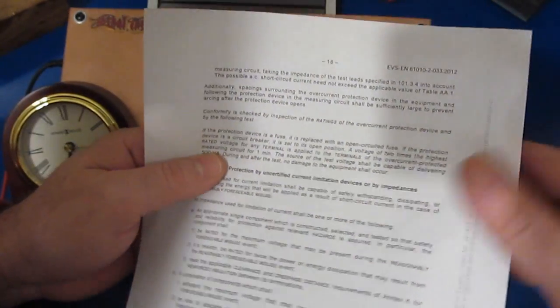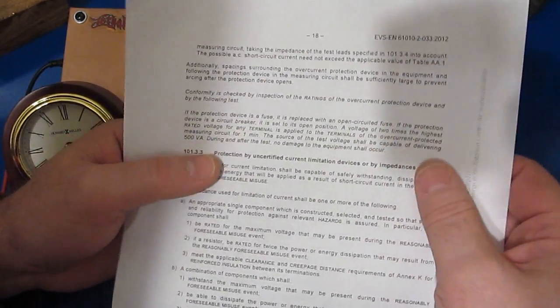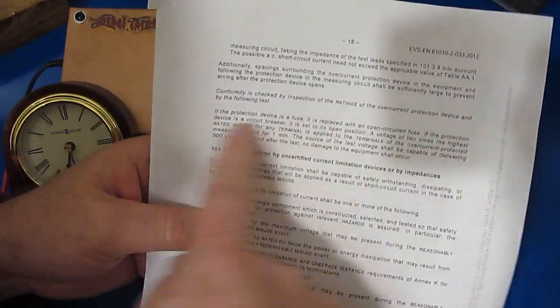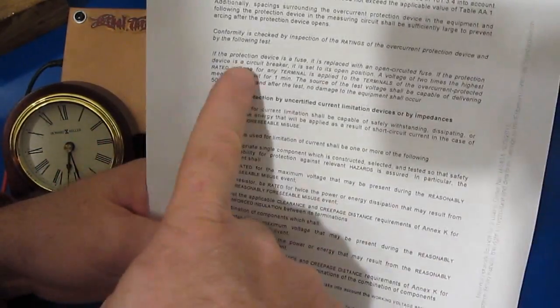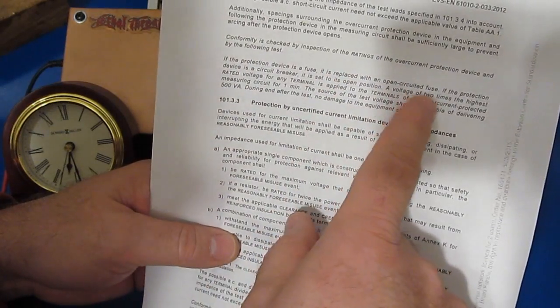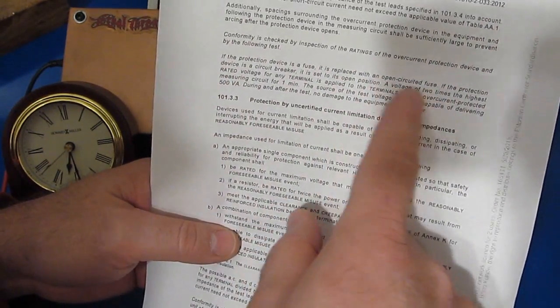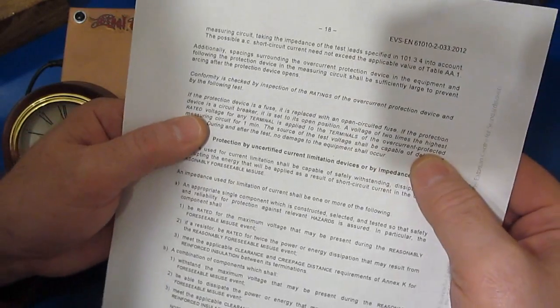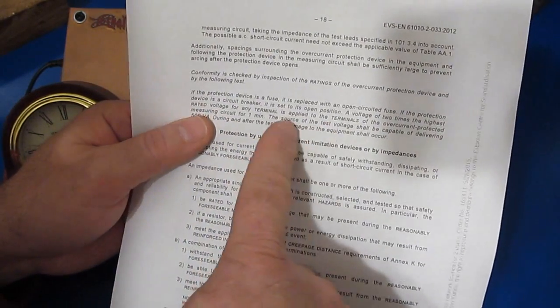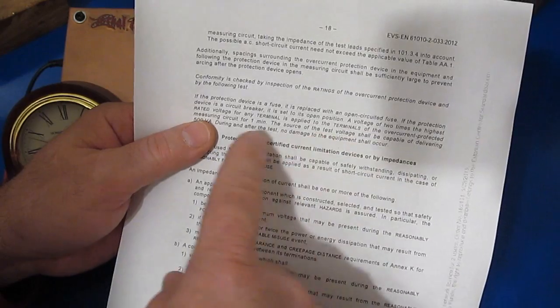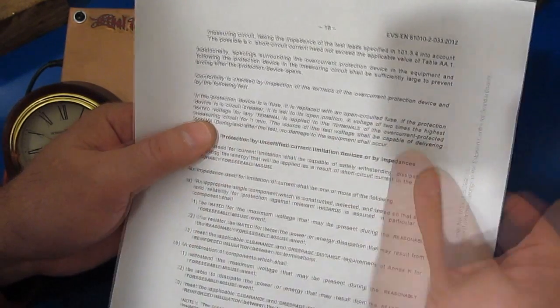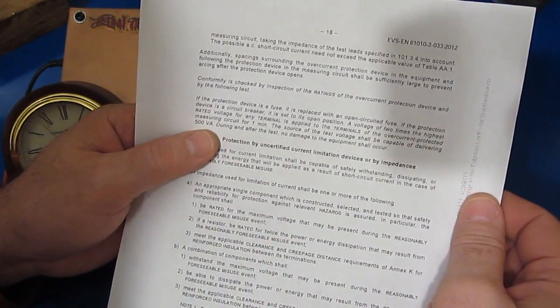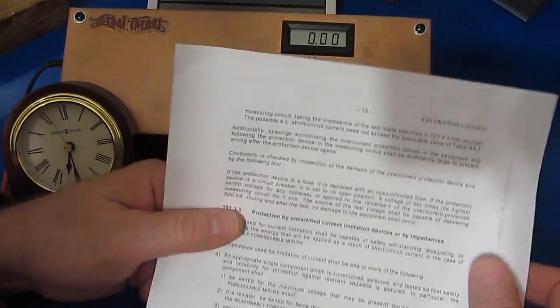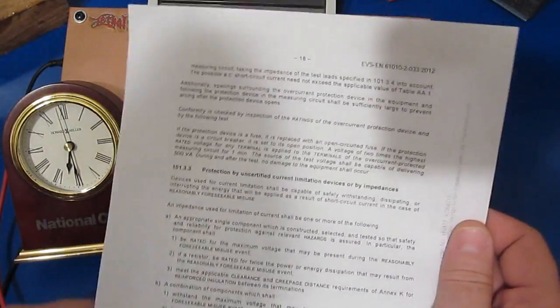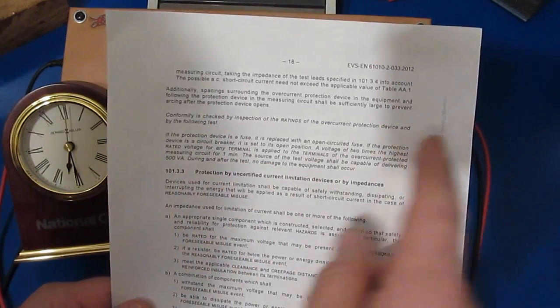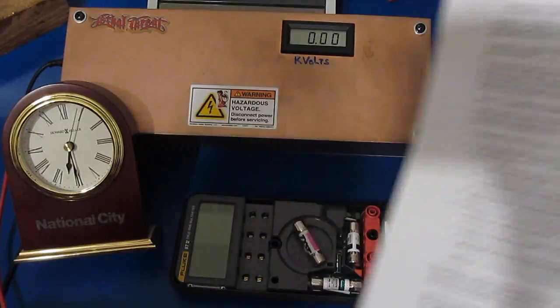So we're looking at IEC 61010-2, and in this section we're talking about the fuse inputs. We're replacing this with an open circuited fuse, and applying a voltage that is 2 times the highest rated voltage for any terminal, applied to the overcurrent protected measuring circuit for 1 minute. The source of the test voltage shall be capable of delivering 500 VA. This power supply can't come close to that, but I am looking for any kind of breakdown to occur.